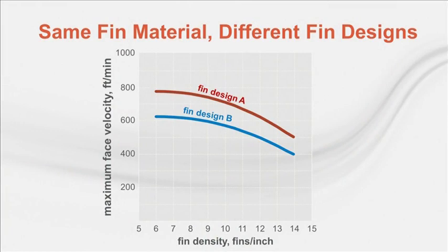Extensive testing of various fin designs and materials has resulted in a clearer understanding of how these factors affect moisture carryover. A chart showing laboratory-tested performance depicts maximum face velocity to prevent moisture carryover on the y-axis versus fin density on the x-axis. Moisture carryover is more challenging at higher fin densities where fins are more closely packed together. The chart also demonstrates the impact of fin surface design — fin design A is engineered to perform at higher coil face velocities without moisture carryover compared to fin design B, even with fins of the same material.